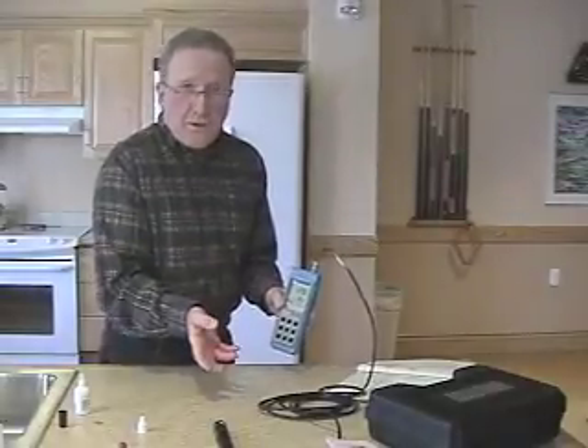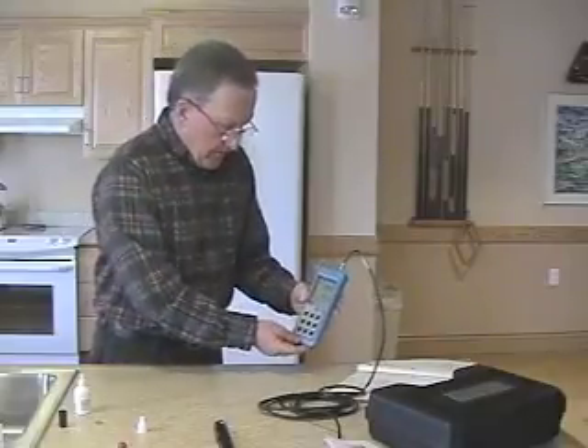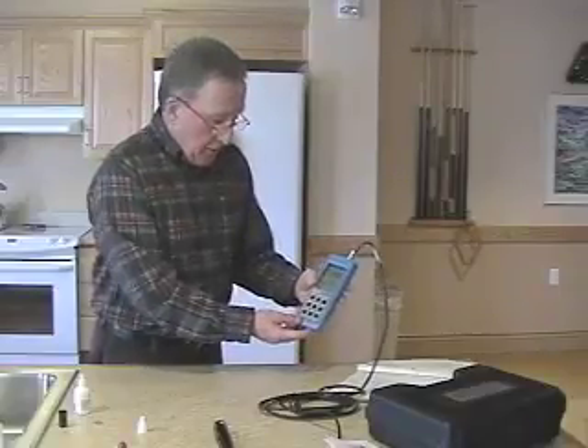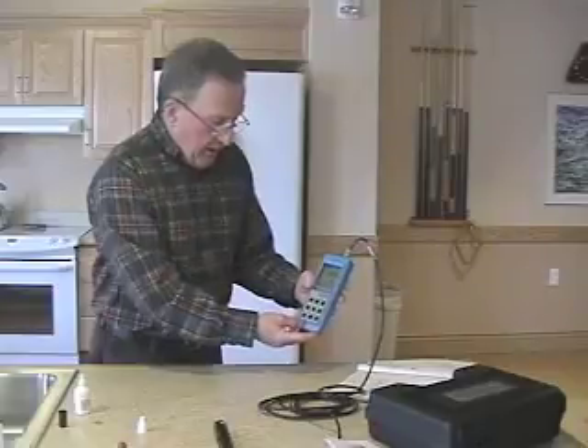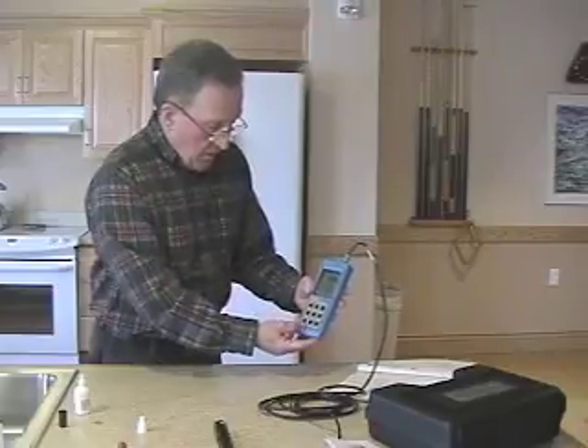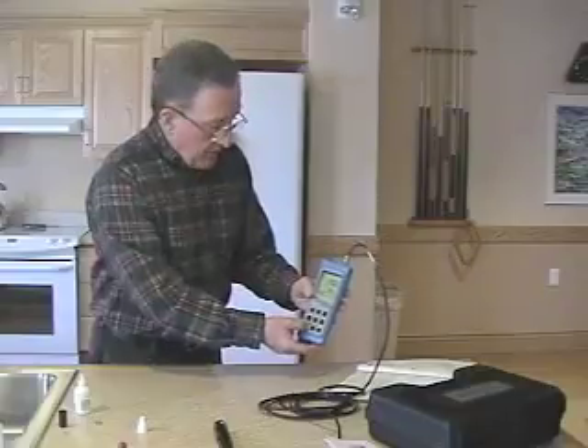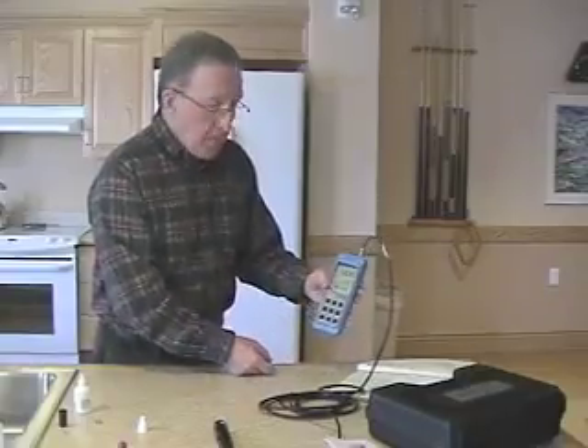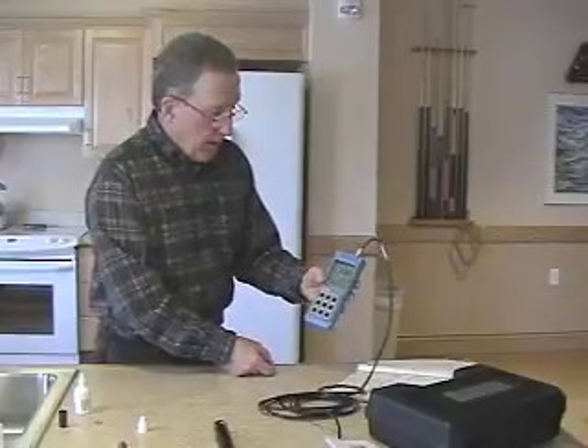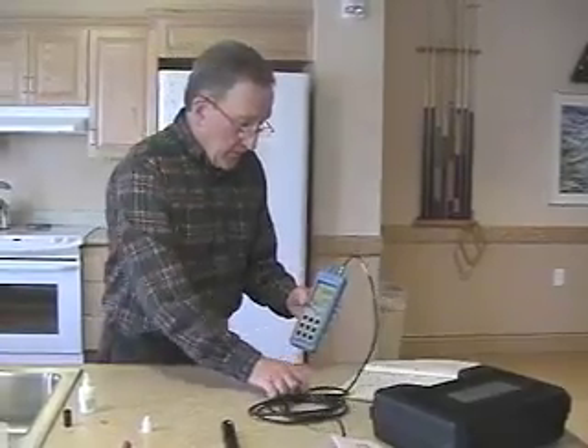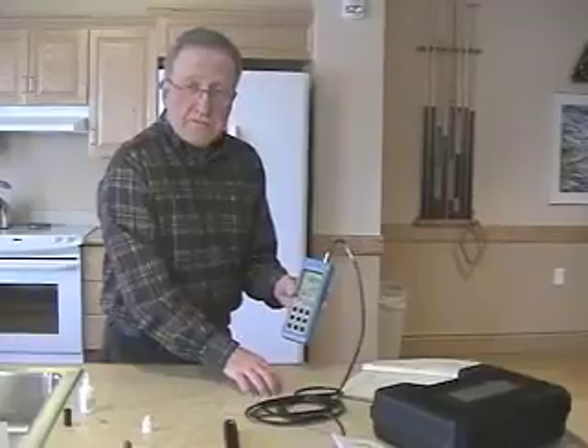Since it's in increments of 100 meters, it could be difficult to get an exact altitude. So you're just going to have to either round up or down to the nearest 100 meters. Okay. Now the meter's calibrated. So to get out of the calibration mode and back into the sample mode, hit the setup button again. Brings us back to our dissolved oxygen reading and our temperature reading. So we're ready to go out and run dissolved oxygen and temperatures.